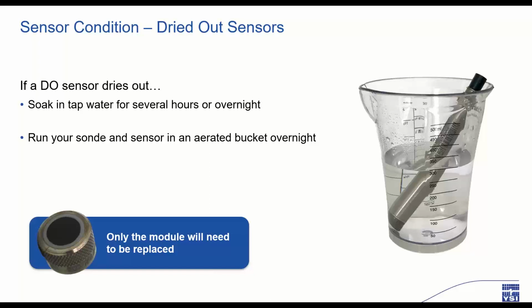on the sensor. If after all of your best attempts to clean and rehydrate your pH electrodes and DO membrane does not bring them back to life, no problem. Just call our customer service team. Remember that the brains or electronics of that sensor of the DO and the pH do not need to be replaced, just the consumable portion, and we'll be glad to help you out if there's any confusion on that.